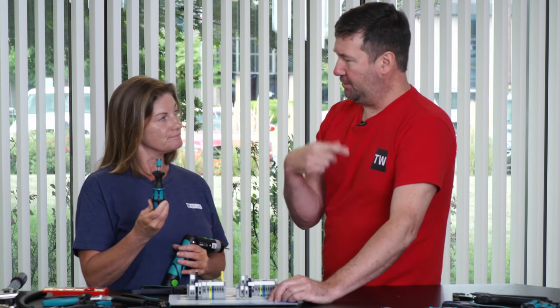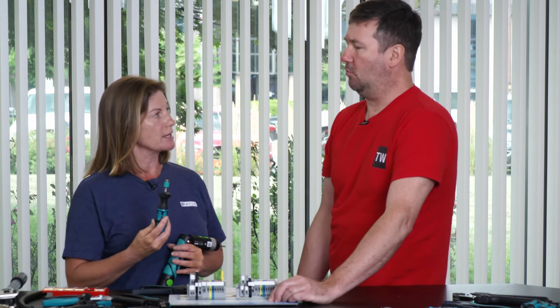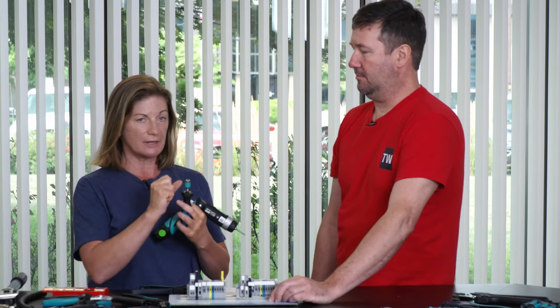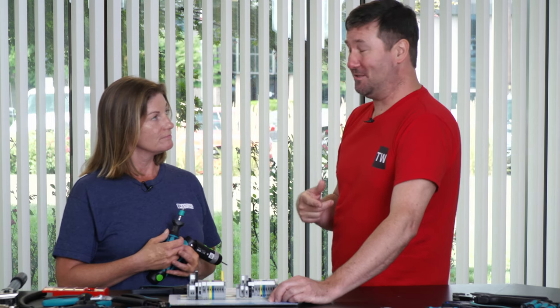When you're not using these, should you back them off? It does help if you back them off a little bit if they're in storage, yes. What happens if you don't? There's a lot of tension on the spring inside, which is obviously going to affect the calibration of the torque screwdriver.